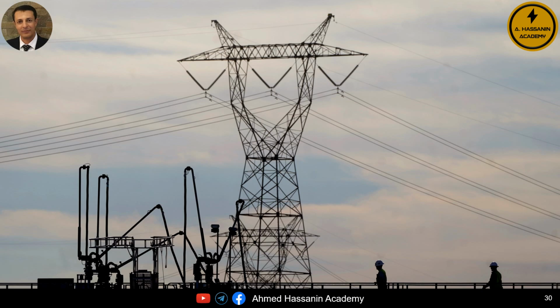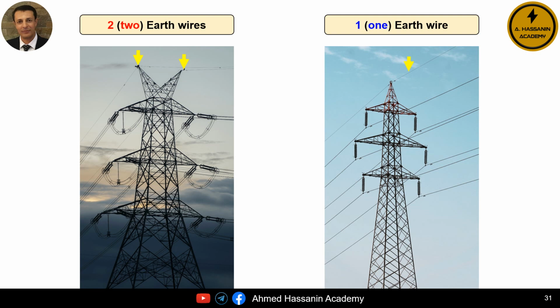In the images in front of us, we see an example of the use of two shield wires or earth wires or ground wires, and of course this is due to the large horizontal distances or horizontal separation between the phase conductors. Therefore, it is essential to understand and know the basis on which the number of shield wires or earth wires or ground wires is selected. Why, in some overhead transmission lines, only one shield wire is used, while in other lines, two shield wires are installed.